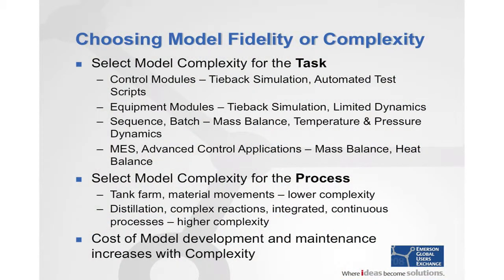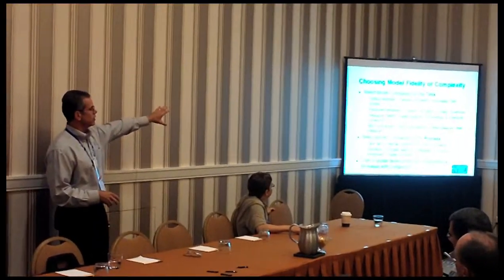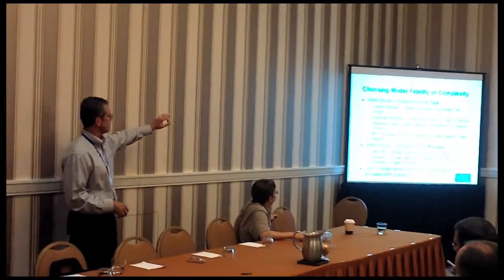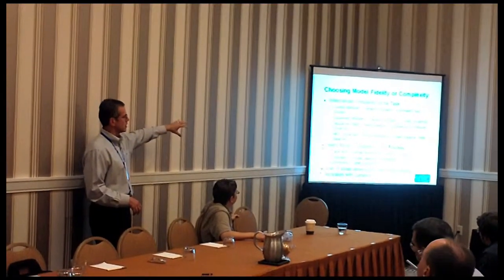The exception is very complex, continuous, integrated processes. In a lot of refining and petrochemical plants, because of the nature of the process, you're going to need a much higher fidelity model — otherwise the reactions and relationships are just not going to be modeled correctly. But you always want to look at what you're trying to do, the task and the process, and selectively apply your models based on the task and the process.